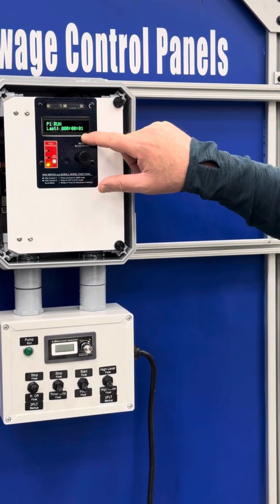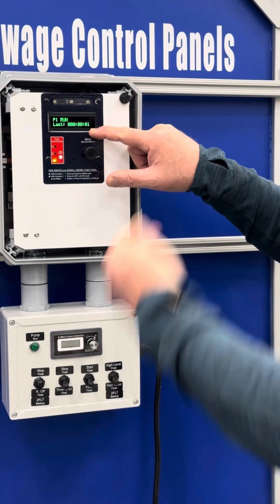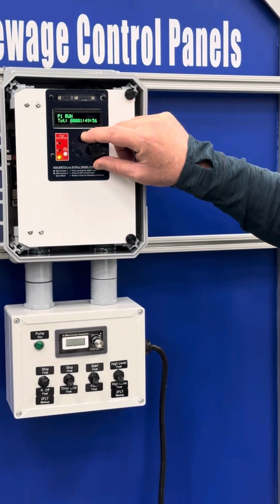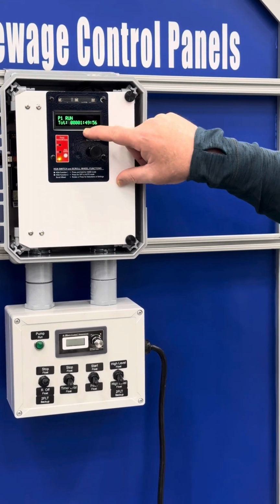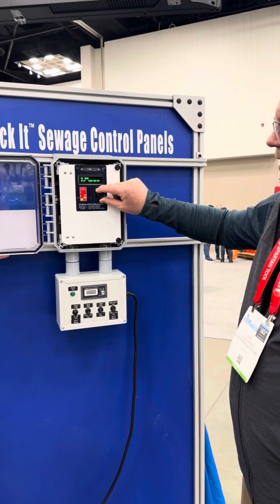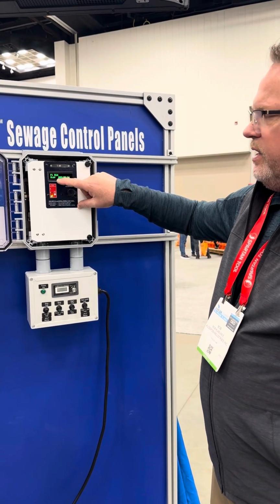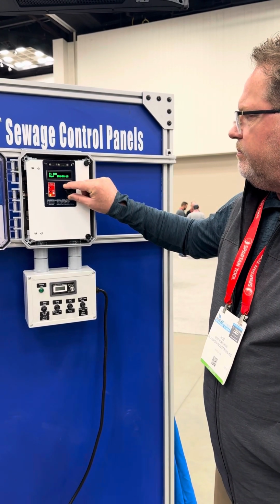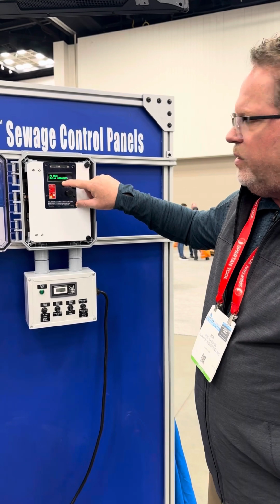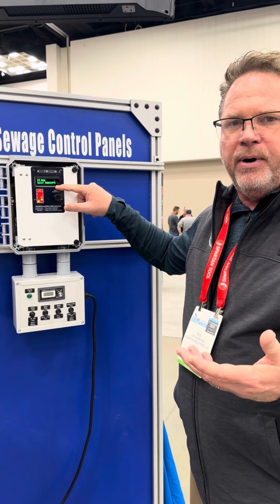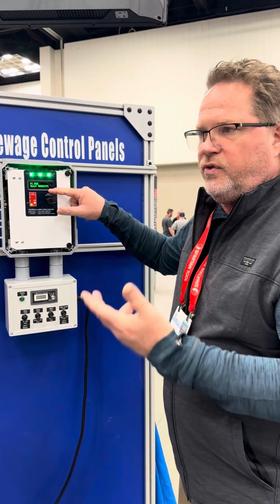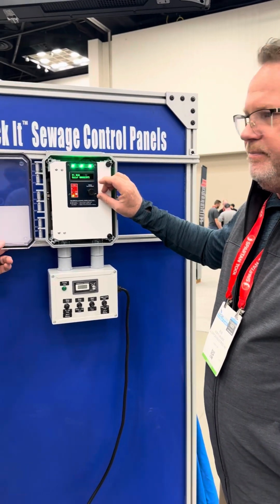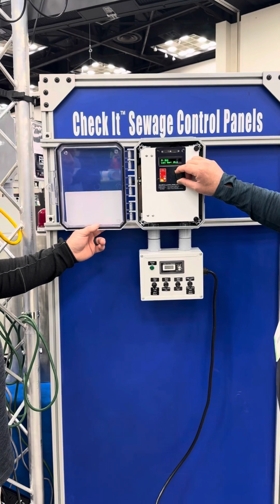So our last time the pump ran was 1 second. We're at a show, so people are flipping switches here, so it's a short run time. But we also give you total elapsed time in hours, minutes, and seconds. We also give you the run time, min, max, and average. And if you enter in a gallon per minute parameter, it'll totalize gallons for you. Nice thing to have for a better understanding of that total water use on the system.